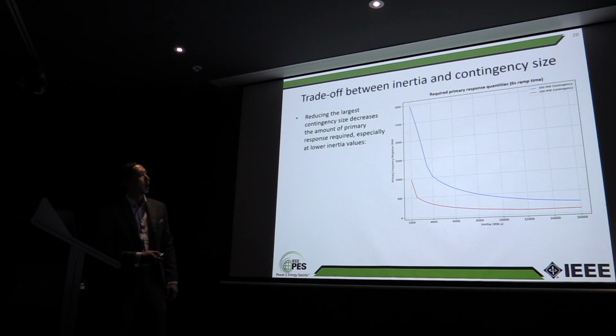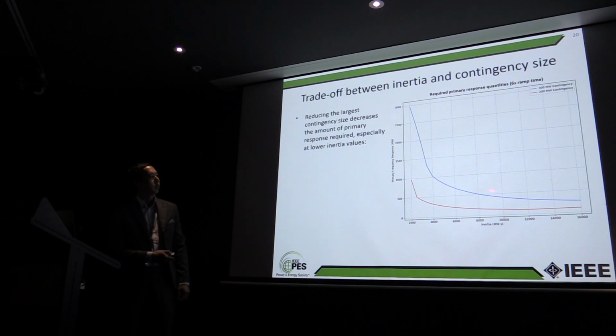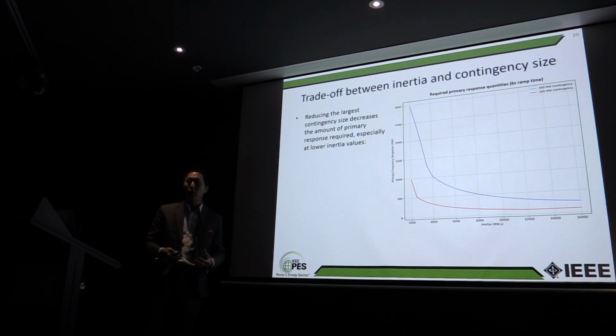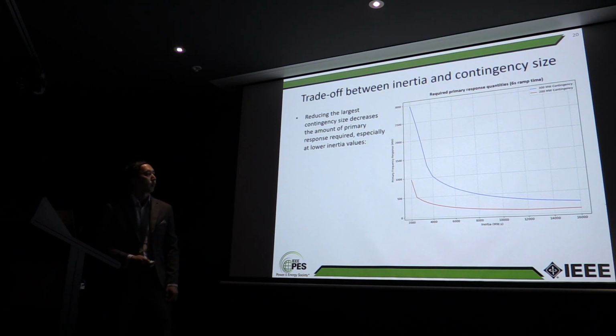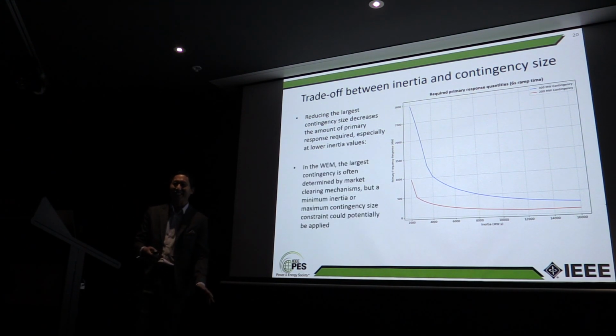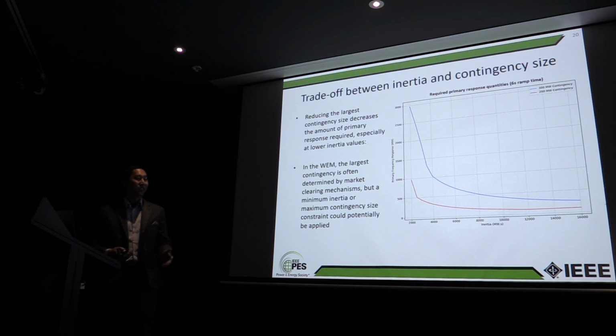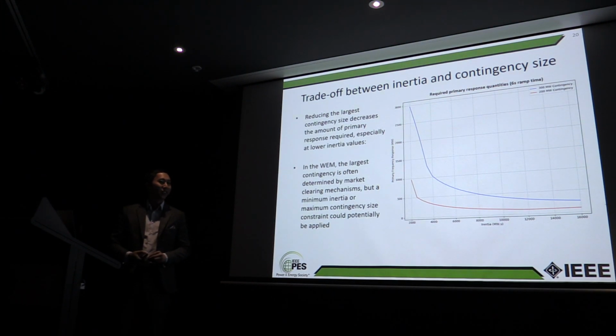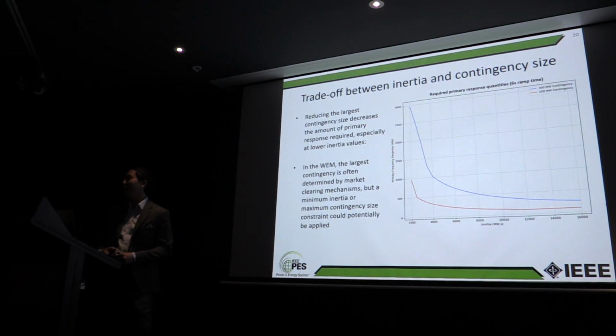So here's a plot here. We have a 300 megawatt contingency here, and we need 3,000 odd here at 2,000 megawatt seconds inertia. If you reduce that contingency to 200 megawatts, you only need about 1,000. So the differences can be very high at very low inertia values. However, in our system, in the WEM, the largest contingency is often determined by market mechanisms. So there's only a few instances where we can control the size of the contingency. So it's determined by market clearing mechanisms. But in the future, it could be that we have a minimum inertia or maximum contingency size constraint that is applied to the system to maintain security.